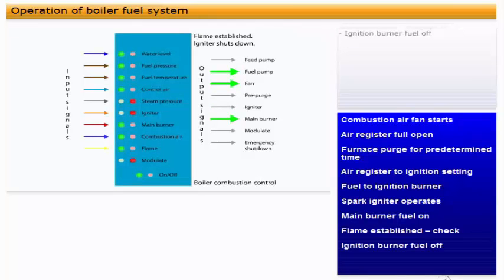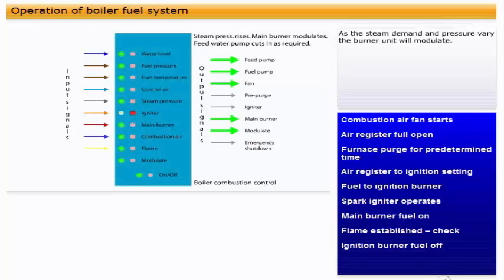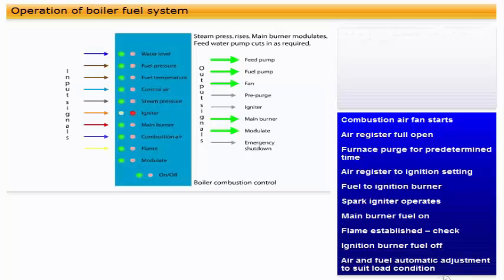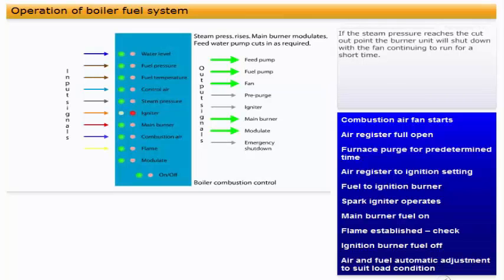As the steam demand and pressure vary, the burner unit will modulate. Air and fuel automatic adjustment to suit load condition. If the steam pressure reaches the cut-out point, the burner unit will shut down, with the fan continuing to run for a short time. You should always make sure you are familiar with the actual system fitted to the boiler on your vessel.